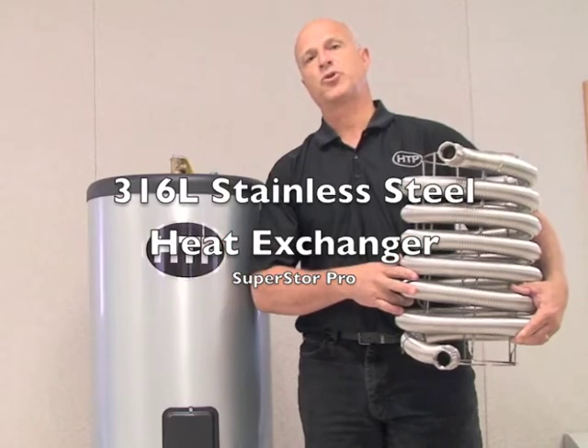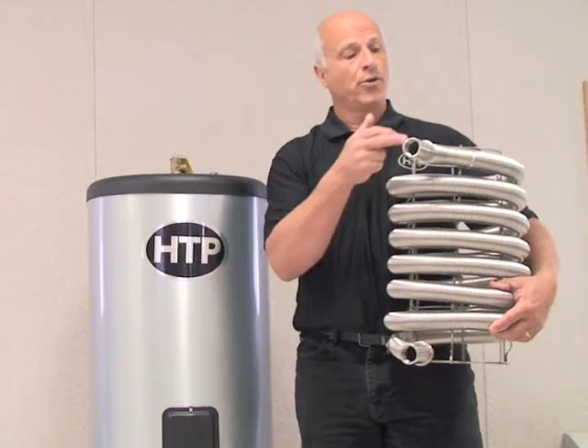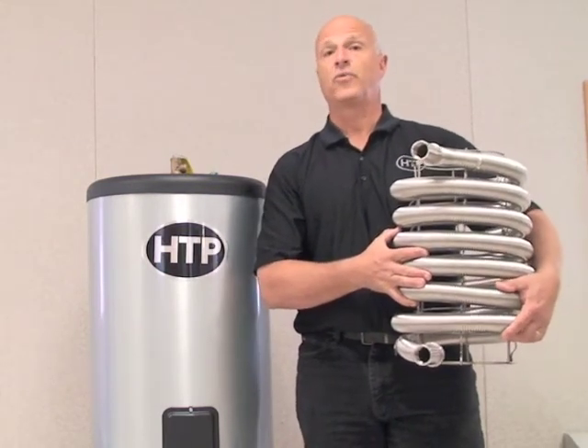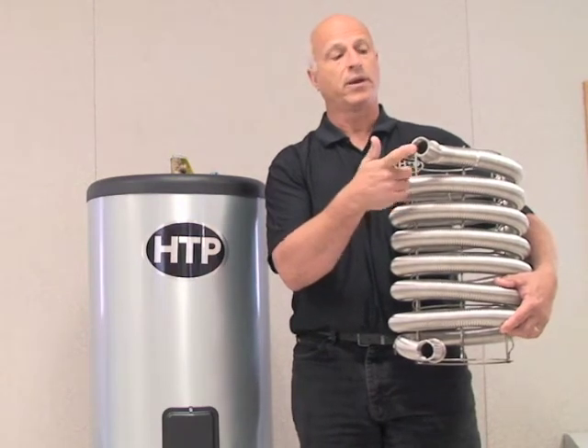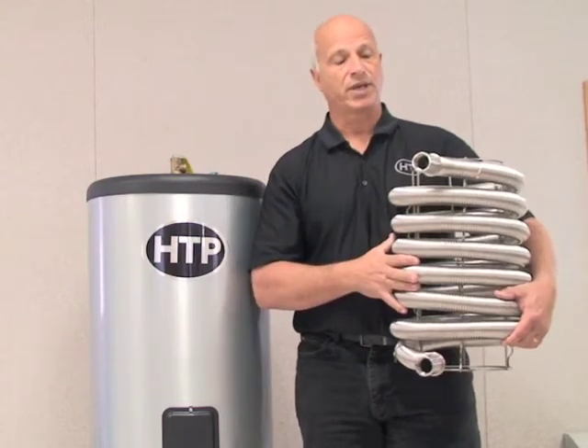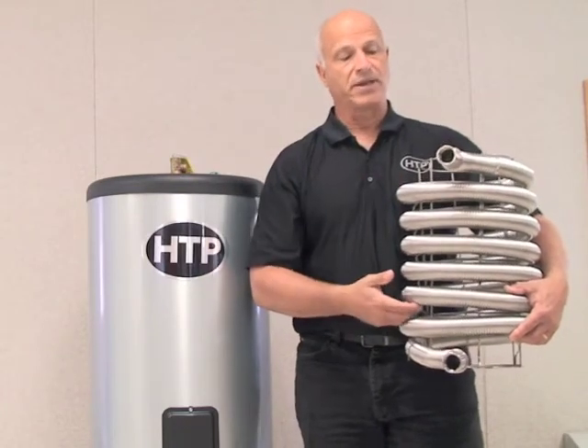One of the main features of the SuperStor Pro is the heat exchanger — it's the heart of the unit. It transfers energy from the boiler water through the heat exchanger into the domestic water, and it's designed to rapidly transfer that energy. Most units operate at 180-degree inlet water from the hydronic boiler. This unit can also run as low as 140 degrees, which is a huge benefit for condensing boilers, still delivering a large amount of domestic hot water.